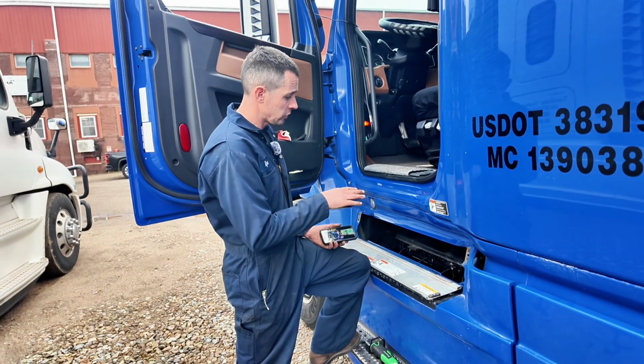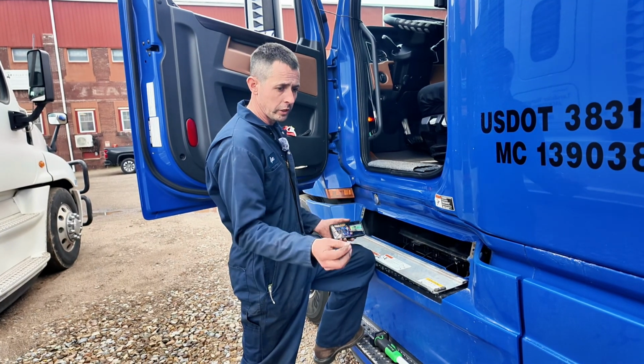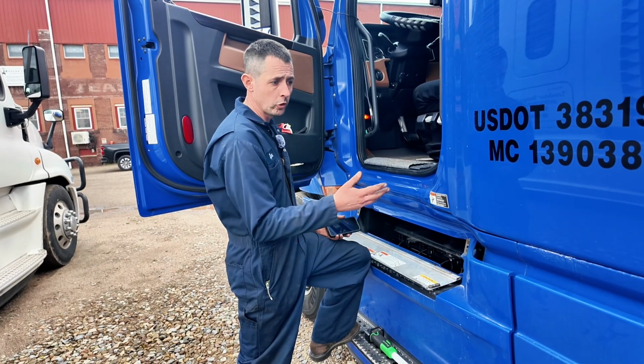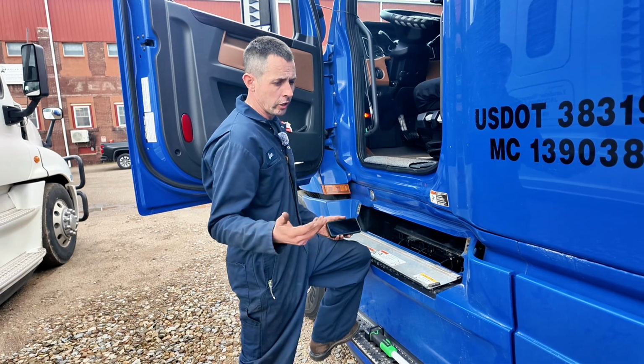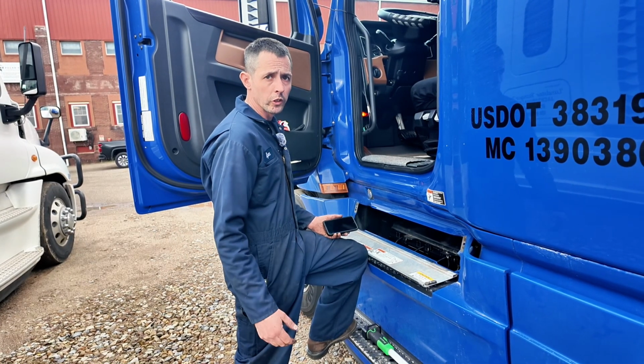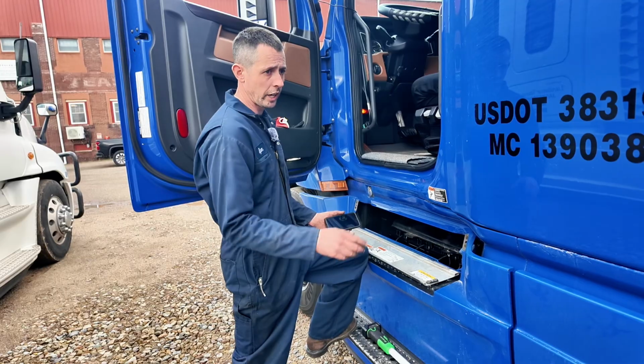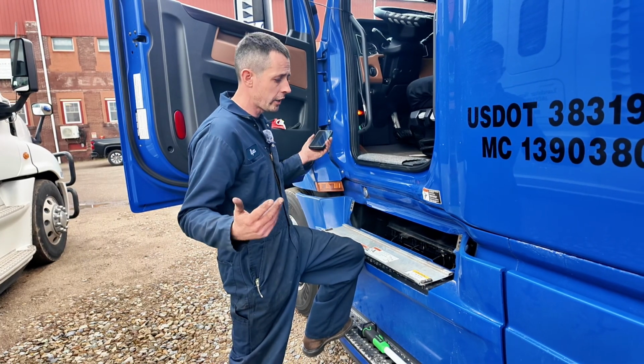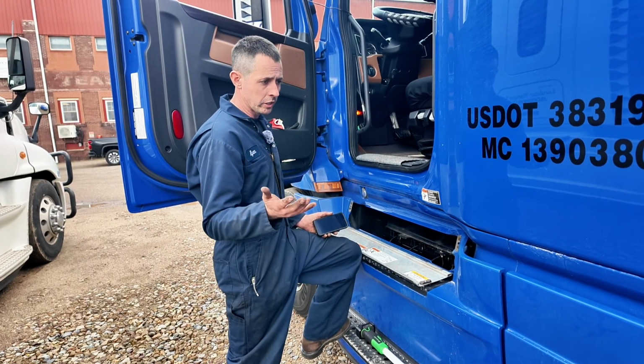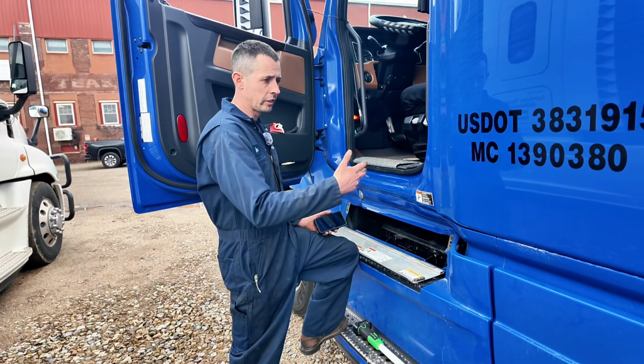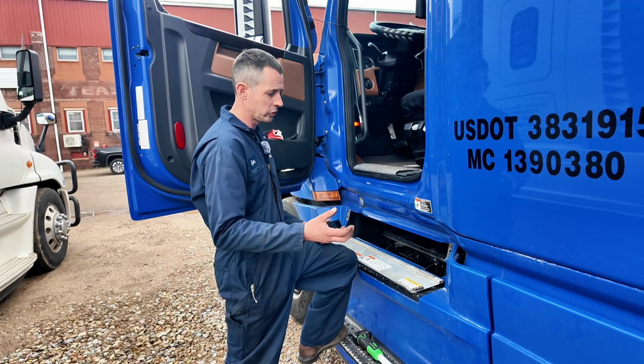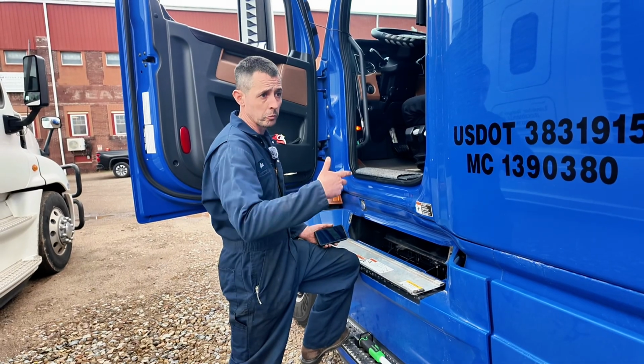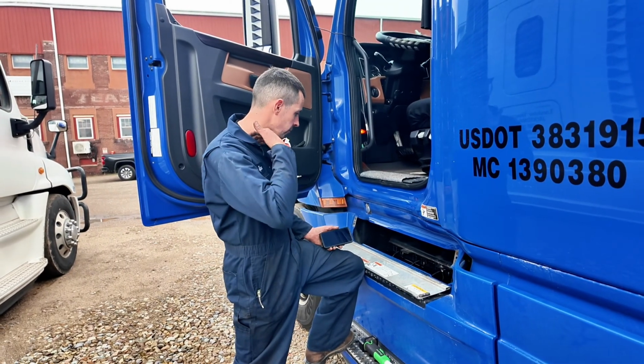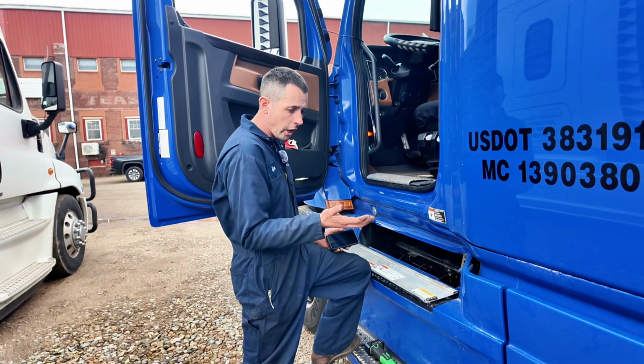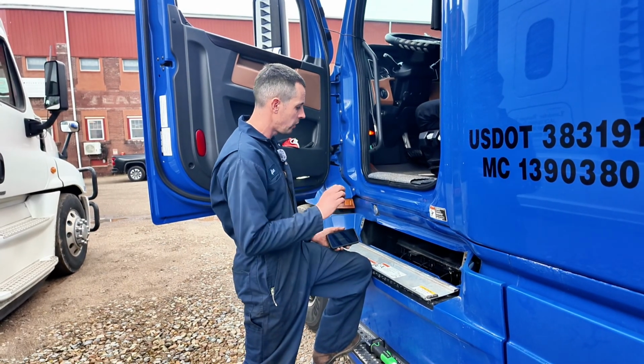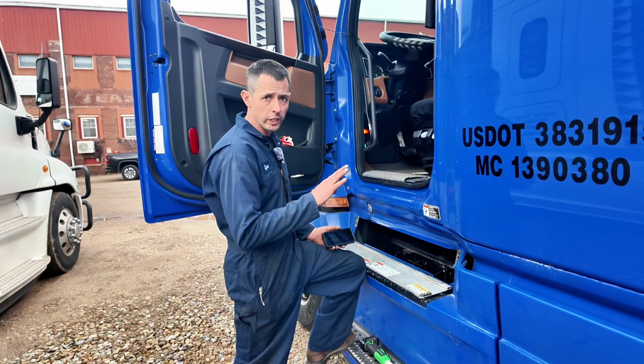So right now, as this is running, pulling that load, we divide our 32 amps into 360, and we get about 10 and a half hours roughly of runtime right now at these conditions, with everything running pretty hard, although it's not that hot here right now. When you're in a hotter ambient temperature, the conductors and everything are going to get hotter, so there's more resistance, more amperage, when it's 90 degrees versus 60 here today. So as it's hotter, runtime is going to go down. But right now, we'll see a little over 10 hours in current conditions.